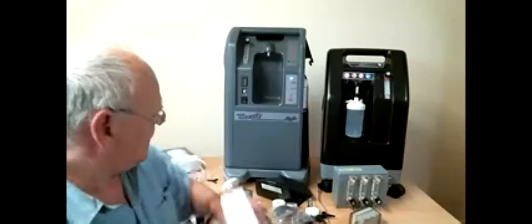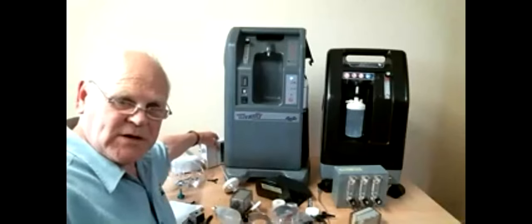back on. But if your power situation is very poor, then you really need to go to an uninterruptible power supply system that is going to give you some battery backup and be able to stabilize both the voltage and the frequency. This is the problem when people put inverters on equipment. It will change the voltage, but it will not change the frequency. Then you're still either under or overpowering the piece of equipment, and that will reduce the life of it considerably.